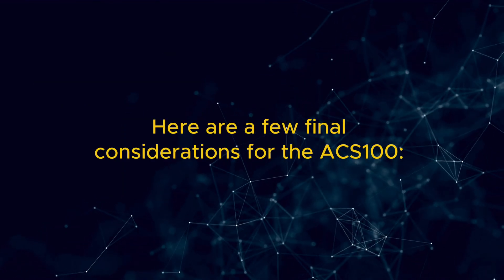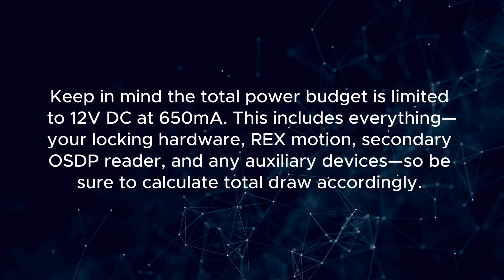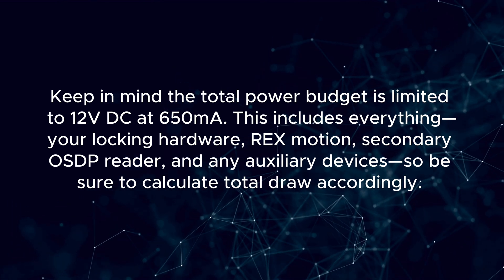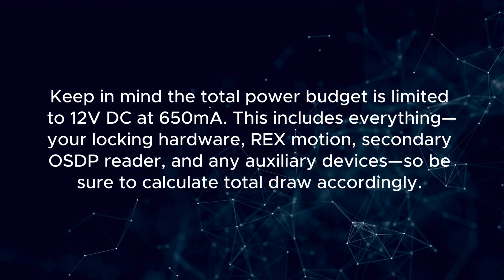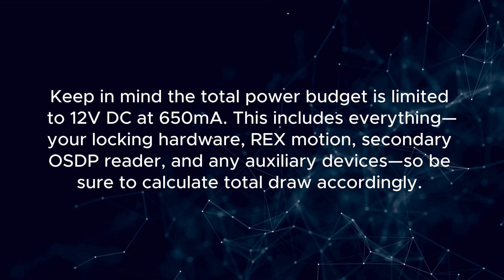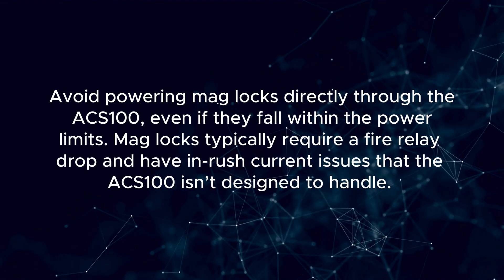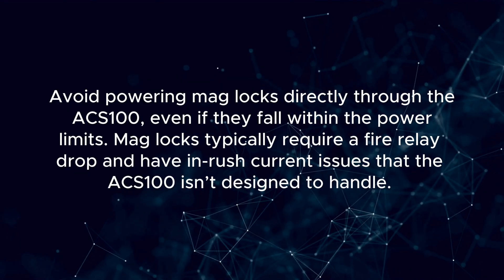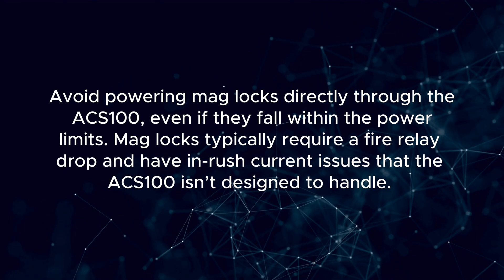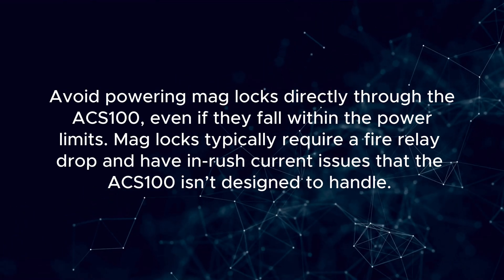Here are a few final considerations for the ACS100. Keep in mind the total power budget is limited to 12 volts DC at 650 milliamps. This includes everything — your locking hardware, REX motion, secondary OSDP reader, and any auxiliary devices — so be sure to calculate total draw accordingly. Avoid powering mag locks directly through the ACS100, even if they fall within the power limits. Mag locks typically require a fire relay drop and have inrush current issues that the ACS100 isn't designed to handle.